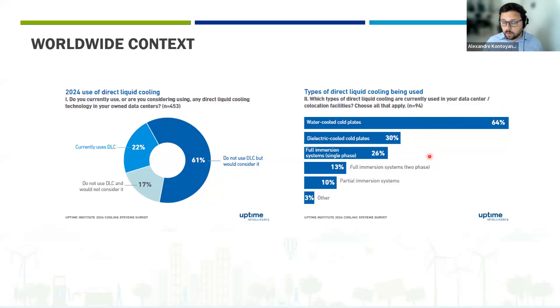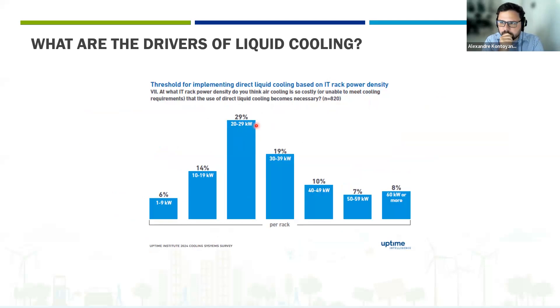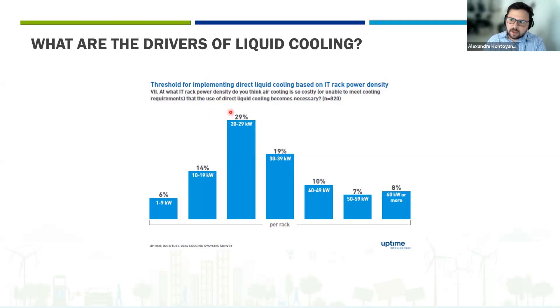The Uptime Institute also asked people what the threshold is to implement liquid cooling based on rack power. Most respondents said around 20 to 29 kilowatts per rack. But if you do the math, you can cool a rack with air cooling systems up to 55–60 kilowatts. So why do people think they need to go to liquid cooling beyond 30 kilowatts? In my opinion, this question is wrong.